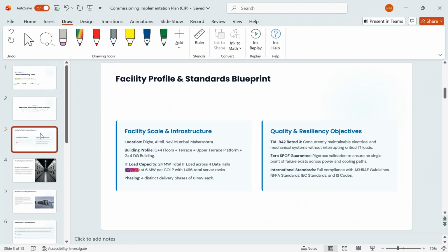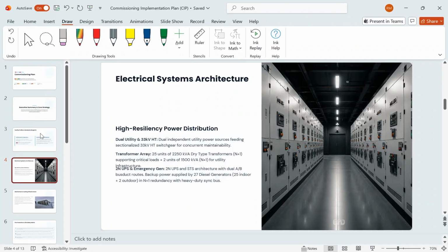Let's deep dive into what its electrical system architecture and mechanical systems look like. For the electrical system architecture, it has a 33 kV dual supply, meaning two independent feeders are feeding the facility at 33 kV from the switchgear. It has 25 units of 2250 kVA dry type transformers with N plus 1 redundancy, plus N plus 1 redundant 1500 kVA utility transformers, two numbers. It has 2N configuration at UPS and emergency generators. It has 27 diesel generators, 25 indoor and 2 outdoor, plus 1 redundancy with a heavy duty sync bus. So this is about the electrical architecture, what the facility speaks about itself.